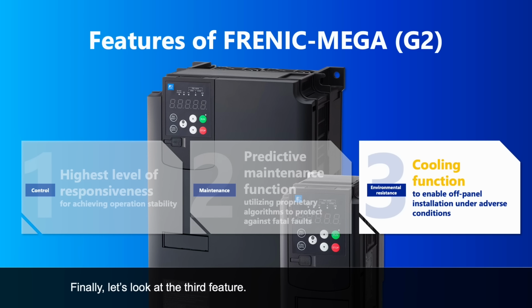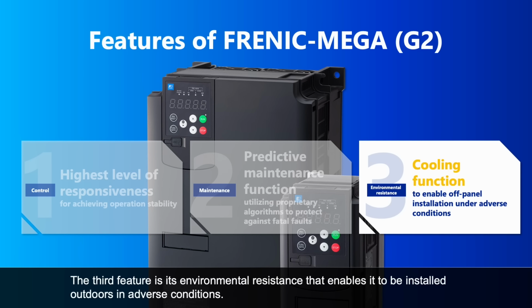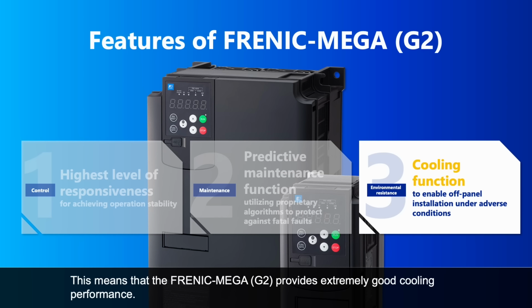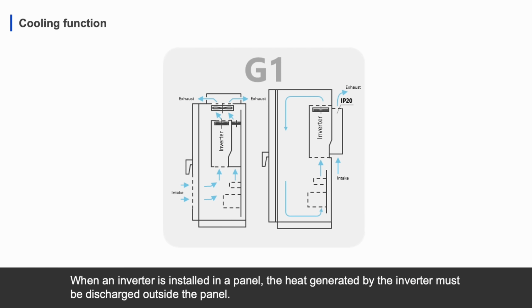Finally, let's look at the third feature. The third feature is its environmental resistance that enables it to be installed outdoors in adverse conditions. This means that the FRENIC-MEGA G2 provides extremely good cooling performance. When an inverter is installed in a panel, the heat generated by the inverter must be discharged outside the panel.